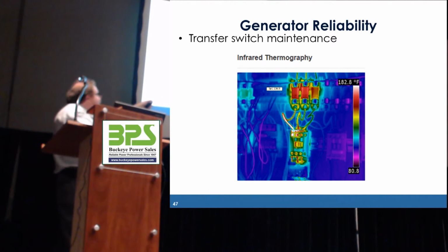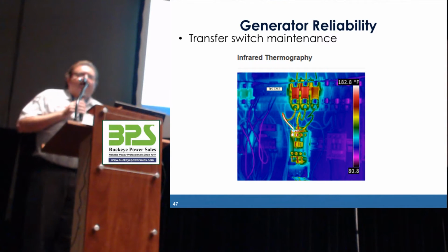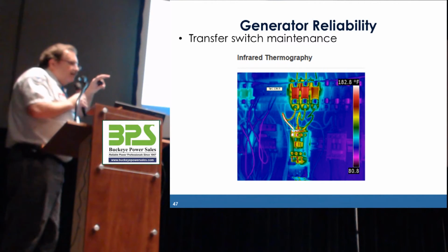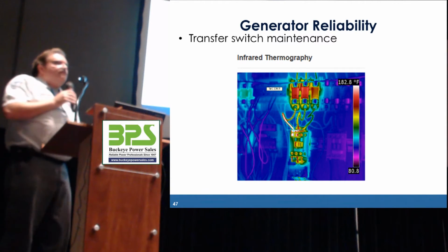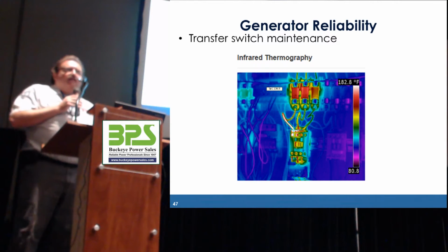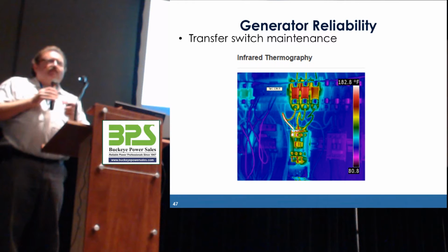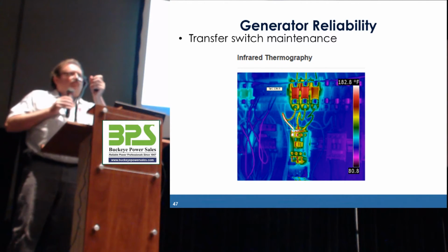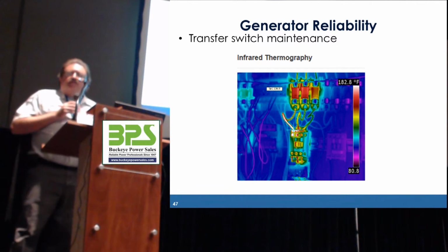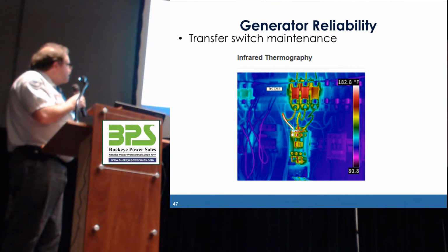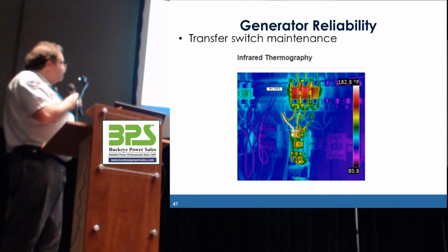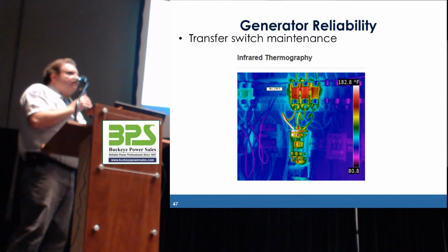This is a picture, we were talking about the infrared technology that we use for maintenance. Again, you have to put on the proper PPE. In our lightning round video, you saw the technician with the PPE open the transfer switch door with the infrared camera and take a picture. Like it was discussed, you have to put it under load to be able to see it. The darker, the redder the color, the higher the heat, right?